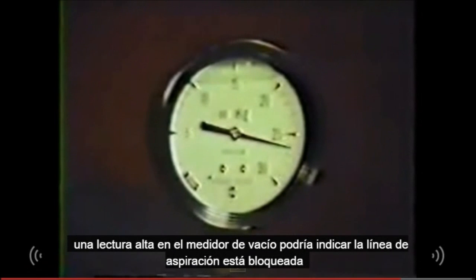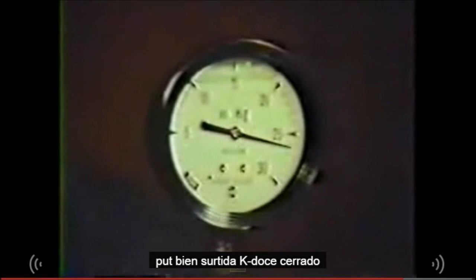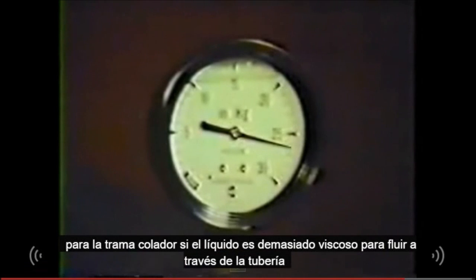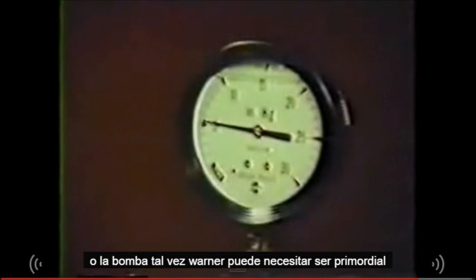A high reading on the vacuum gauge might indicate the suction line is blocked, foot valve stuck, gate valve closed, or the strainer plugged. If the liquid is too viscous to flow through the piping, the lift too high, or the suction line too small, the vacuum gauge reading would also be high. A low reading on the vacuum gauge might be caused by an air leak in the suction line. The end of the suction pipe may not be in the liquid, or the pump may be worn or may need to be primed.